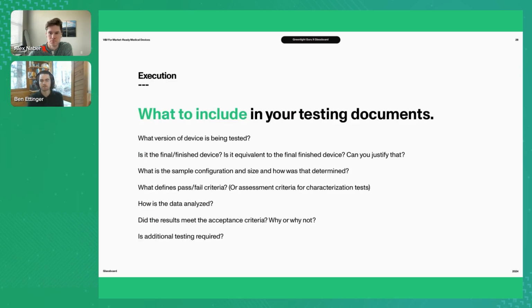And then boots on the ground for execution. What actually explicitly gets included in your testing documents? We need to look at what version of the device is being tested, whether that is the final and finished device, or if it is equivalent to the final and finished device, and if we can justify it. So having that documentation in place to paint a clear picture of any gaps between what we're calling equivalent and what is production.